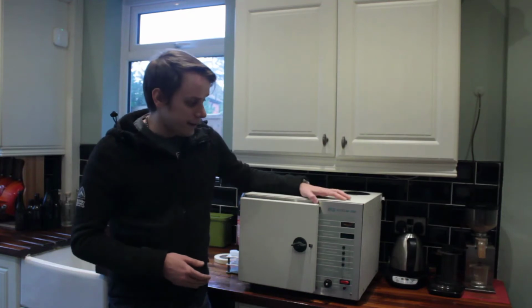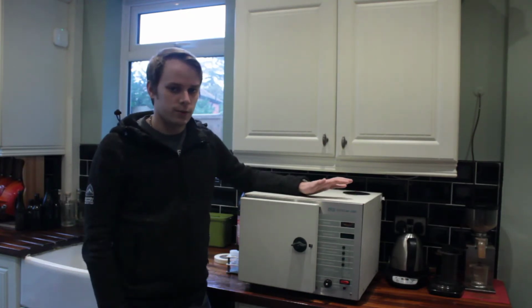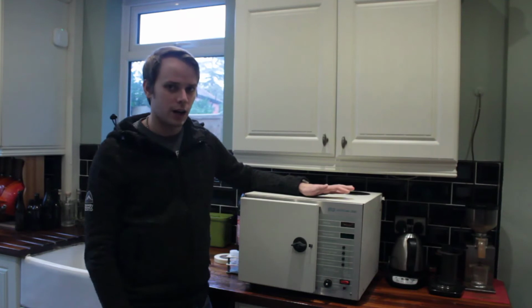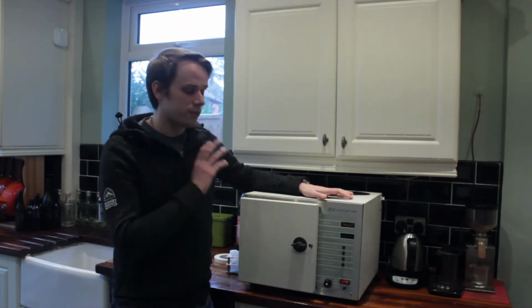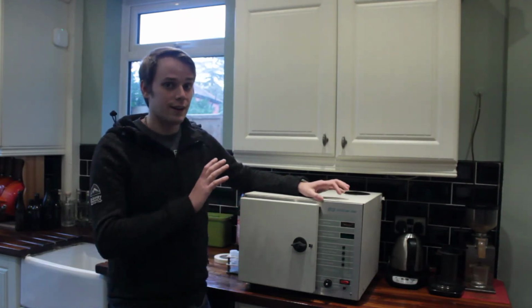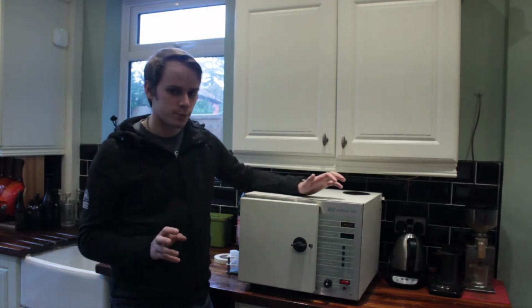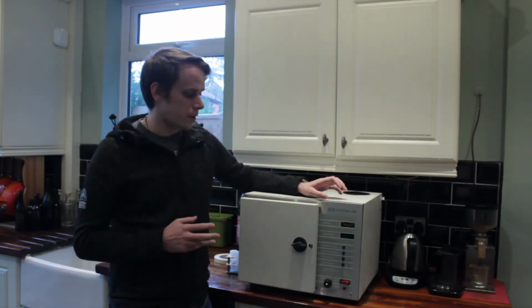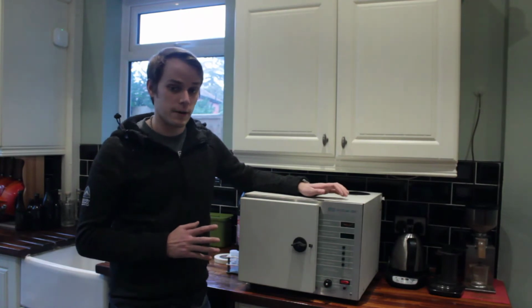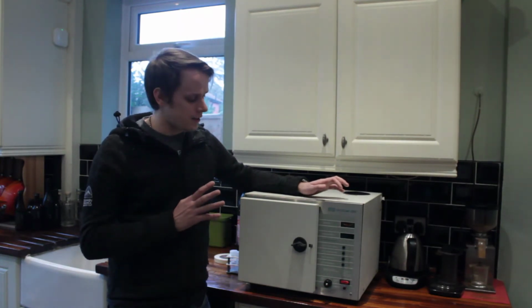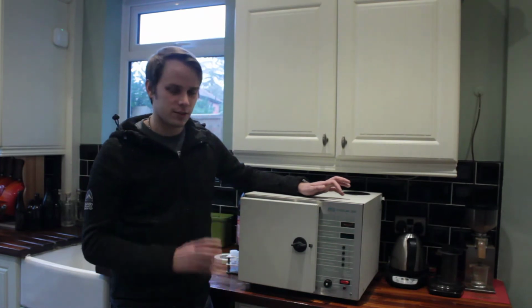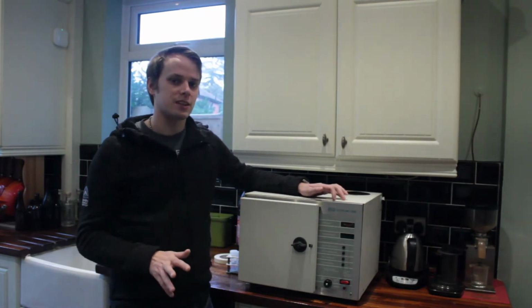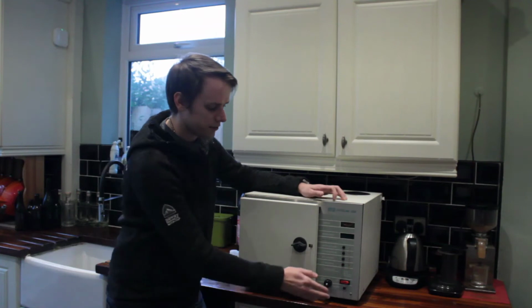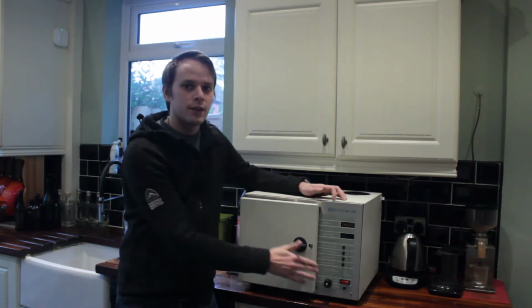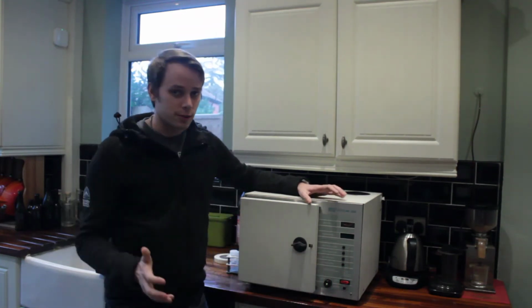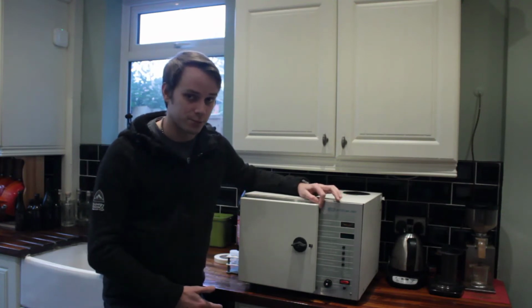This autoclave here is an SES 2000. I think it's quite an early one. Judging by the serial numbers on the different parts of the machine, I think it's from around about the late 80s. We got it for about 150 quid off of eBay. And annoyingly, this early model is slightly different to the one that the manuals are available for online. This has a manual fill valve on it. The newer models that are far more common have an automatic fill on them.